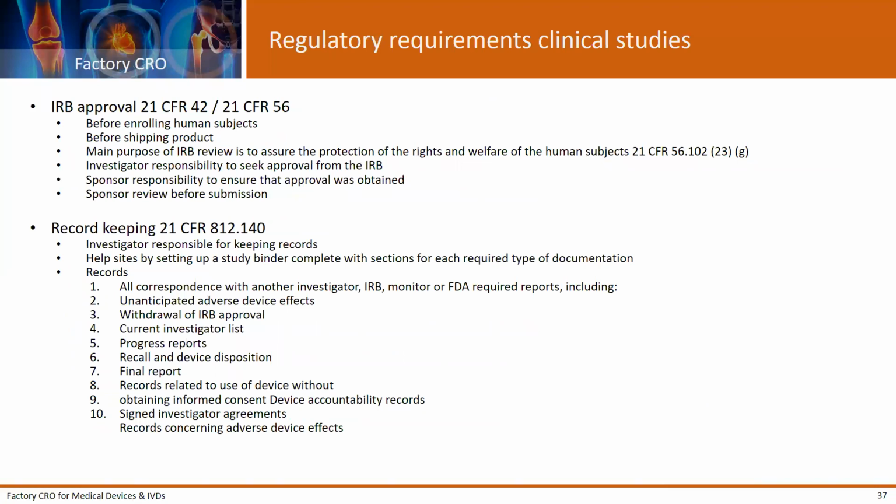Always you need IRB approval for clinical trials under an IDE, but also if you perform post-market studies for marketed devices, you should go to an IRB and request approval. And you see the 21 CFR 56. This is not the 812. It is always applicable to any clinical trial.